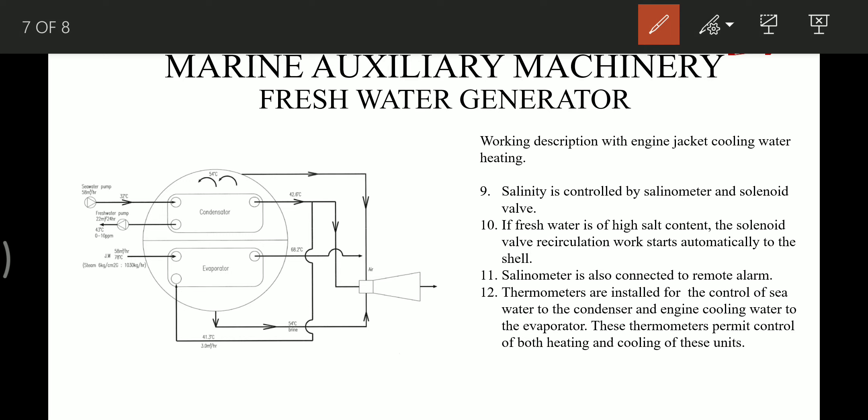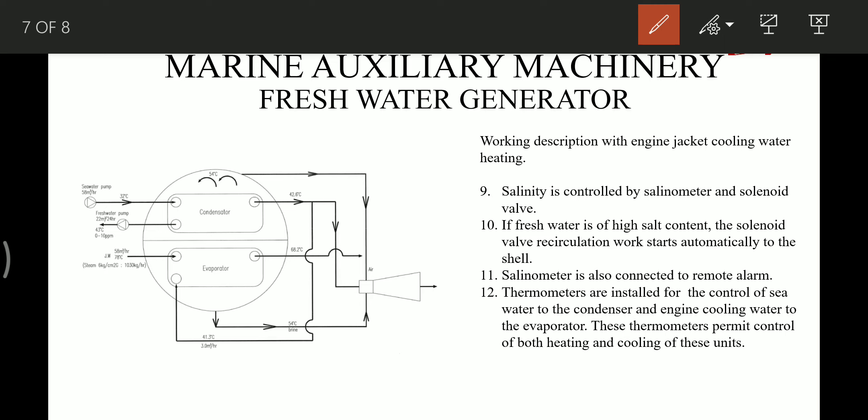Salinity is controlled by a salinometer and solenoid valve. If the fresh water is of high salt concentration, the solenoid valve recirculation works automatically back to the shell. The salinometer is also connected to a remote alarm, so if the salinity of the fresh water produced by the freshwater generator is high, the salinometer activates the solenoid valve and gives an alarm. The activation of the solenoid valve recirculates the produced fresh water of high concentration back to the freshwater generator. Thermometers are also installed for control of sea water to the condenser and engine cooling water to the evaporator, permitting control of both heating and cooling of these units.